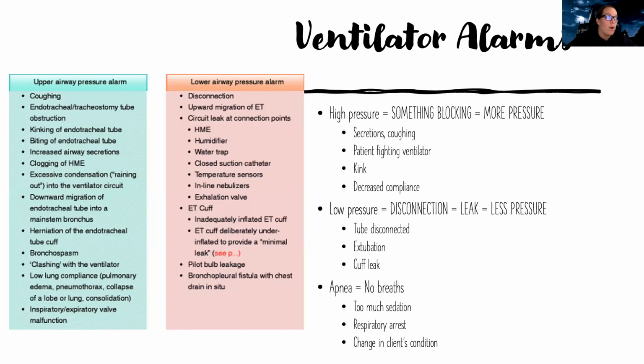So when we think about a high pressure alarm, this is the machine telling me something is blocking me from being able to get air in. There either is literally a blockage, like a kink, or there's something in the way that's causing resistance. So kind of think of this like systemic vascular resistance from cardiac, like there's too much resistance. The ventilator is having to overcome too much resistance to get air in. So this might be because the patient has a lot of secretions. So kind of think about like COPD and asthma, how they have all those secretions in their breathing tubes, and that it's really hard. There's a lot of resistance, so they struggle to get enough oxygen.